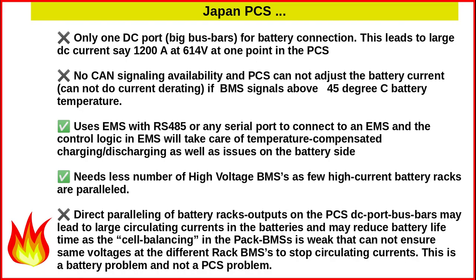Then the Japanese PCS do not have the CAN signaling availability, and the PCS cannot adjust the battery current, that is, it cannot do the current derating automatically if the BMS signals above 45 degrees C battery temperature. But fortunately, the Japanese PCS also comes with a strong EMS, that is energy management system, which is connected via RS485 or any other serial port to the PCS, and the EMS is also connected to the BMSs of the batteries, and the control logic in the EMS does everything that is required.